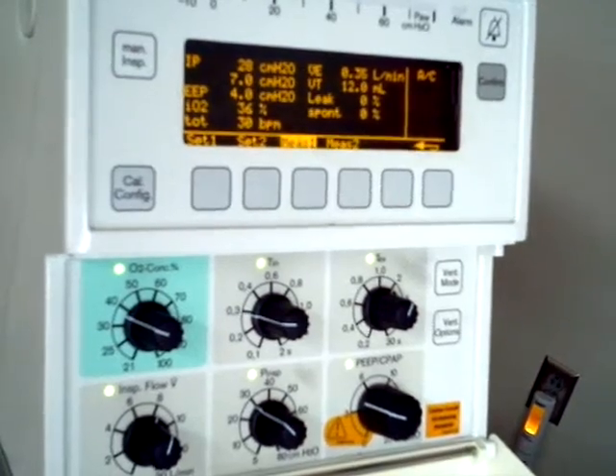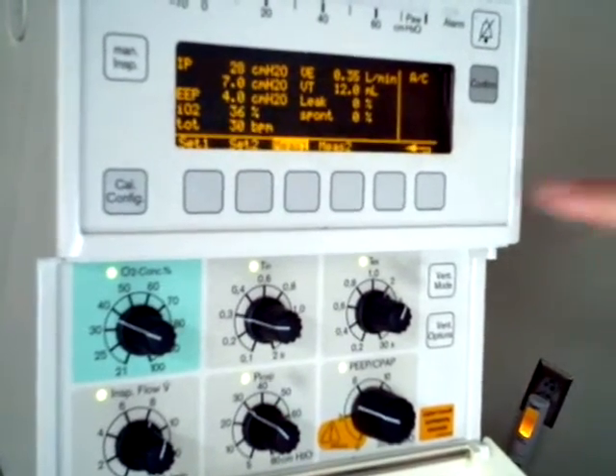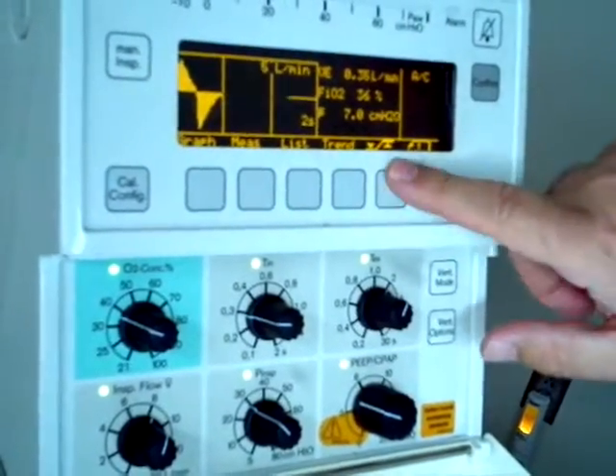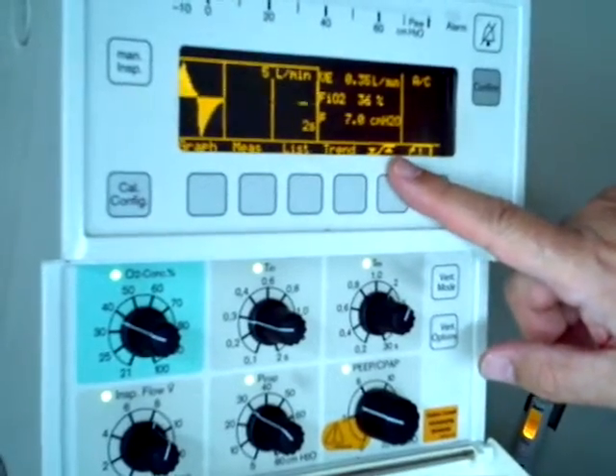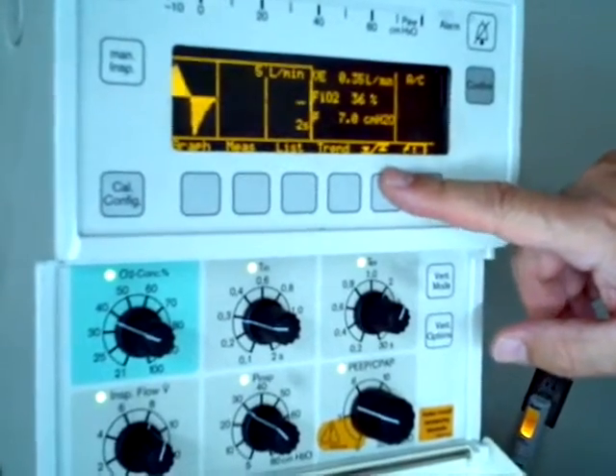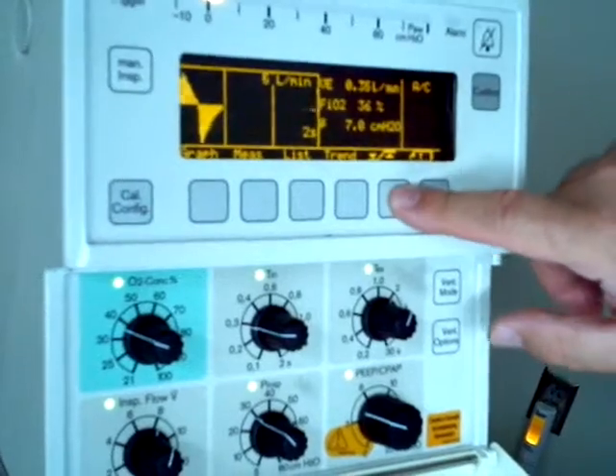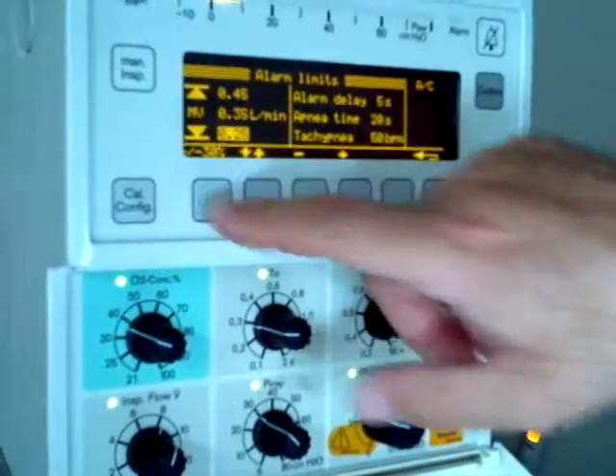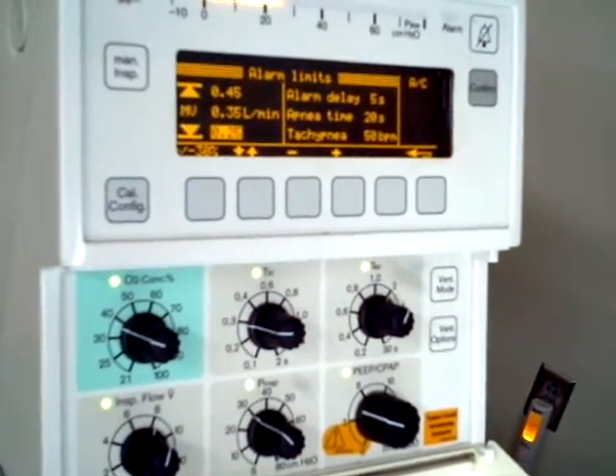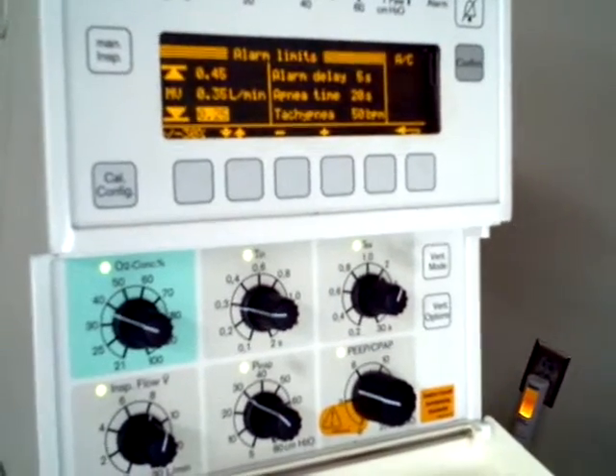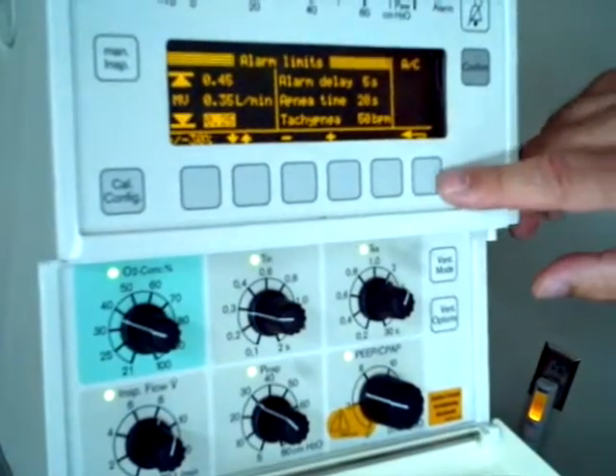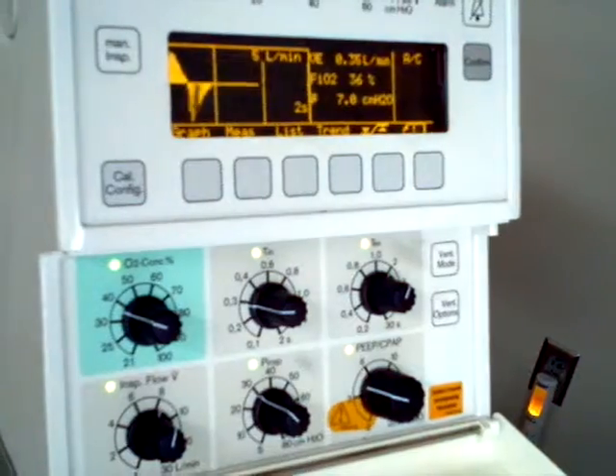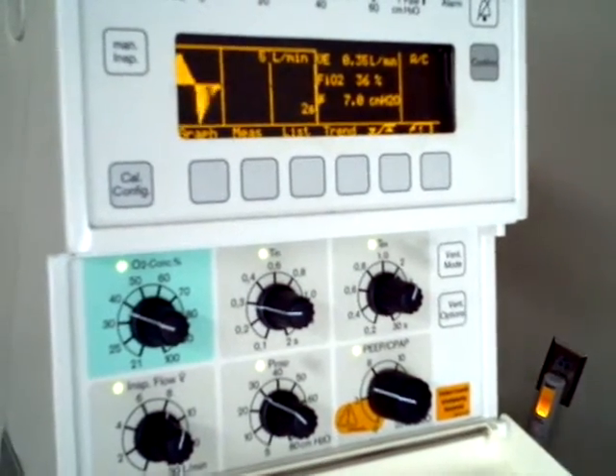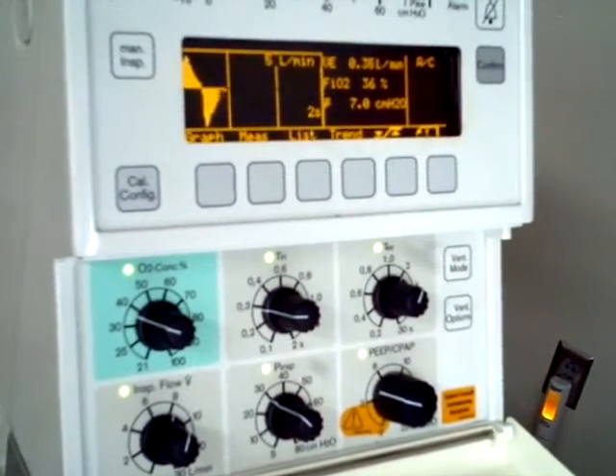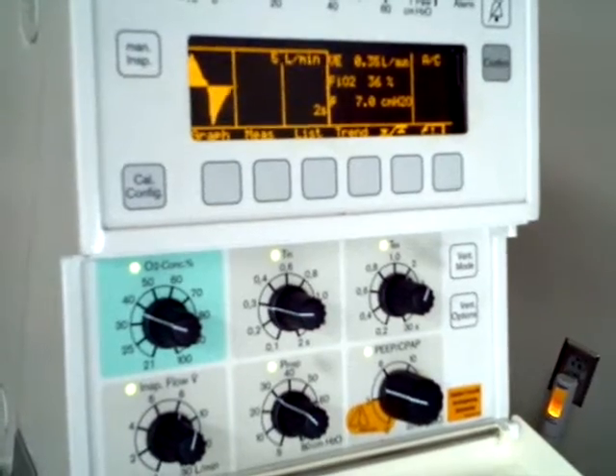My alarm. While this checkoff is going to be making the change, going back to the alarm screen, which is this one here with the up and down arrow key. It's just a symbol. I don't know why it doesn't say alarms, but that's just what they decided to do. When I design my own ventilator, after I write my book, early retirement. All right, so now I have a new tidal volume, new minute volume. My rate stayed the same. I used my PIP to increase my tidal volume.